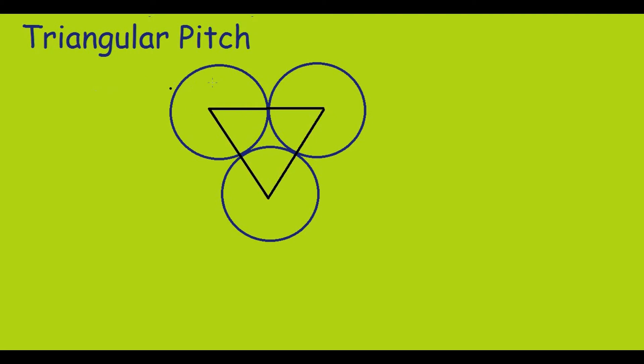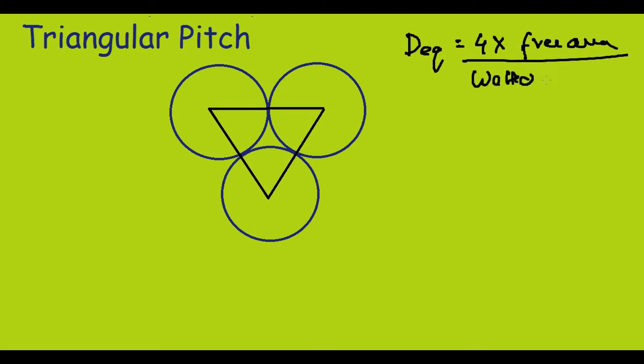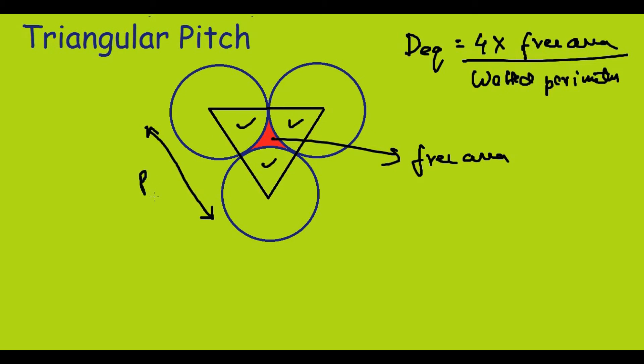Now we will do the same calculation for triangular pitch. We need to find the free area. The red portion in the middle is the free area. To calculate it, we find the area of this entire equilateral triangle and subtract the circular pieces. The side of the triangle is Pt, the diameter of the circles is DO, and the area of the equilateral triangle is (√3/4)Pt².